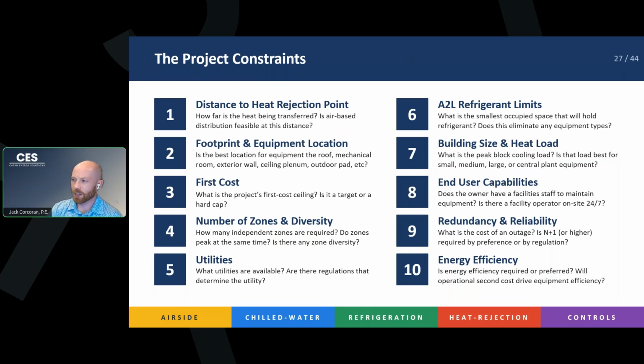Building size and heat load. We're going to have a cap on our capacity, right? So these rooftop units can only get so big before they get pretty ridiculous. You can imagine, or I mean, it makes sense, right? We have more capacity, we have more airflow, and we have bigger ducts. So if we have a 500 ton or 1,000 ton system, we don't want to just use one rooftop unit. That's going to be ridiculous. Our duct is going to be as big as our building. So we want to make sure that when we're picking our system type, that rooftop units have a max size before the ductwork starts getting ridiculous, or maybe it starts taking up too much space on the roof. So that's just another thing to keep in mind.